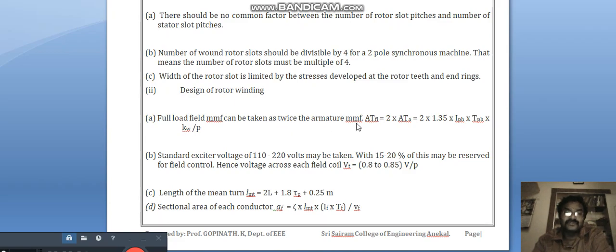Design of rotor winding: full load field MMF can be taken as twice the armature MMF. AT_fl = 2 × AT_a, that is 2 × 1.35 × I_ph × T_ph × kw / p. Standard exciter voltage of 110 to 220 volt may be taken, with 15 to 20% of this may be reserved for field control.